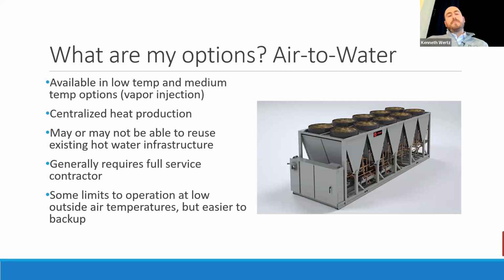So then the options we just talked about, we would refer to as air-to-air heat pumps. So you're taking heat from the air outside and turning it into heat inside the building, in the air inside the building. A different way to do it, that is sort of similar to an air-cooled chiller, would be to take the heat from outside and put it into water and distribute that hot water throughout the building. It's better in that water obviously has an inherent better ability to transfer heat, and you can also potentially reconnect it into your existing systems without having to replace a whole bunch of infrastructure, if things work out well. But we'll talk about the ways that can be more or less likely to work out as smoothly as you'd hope.